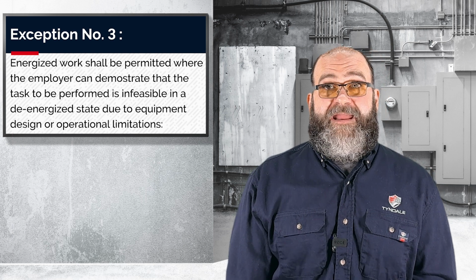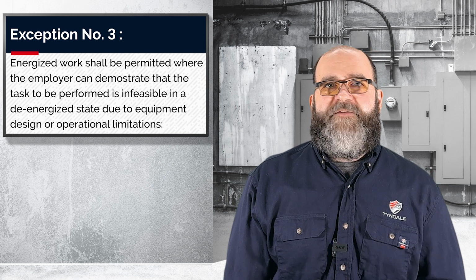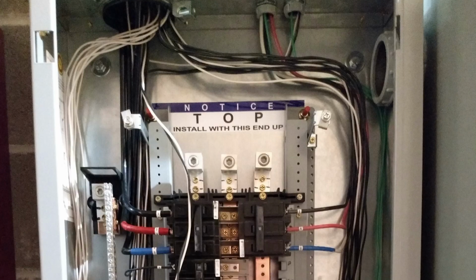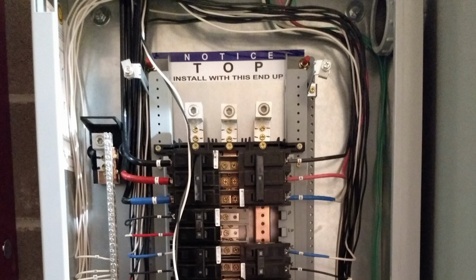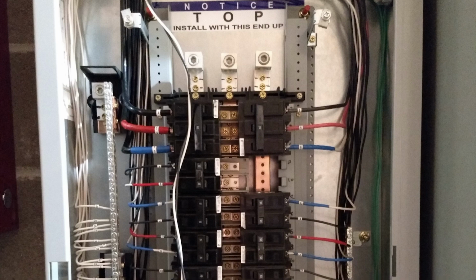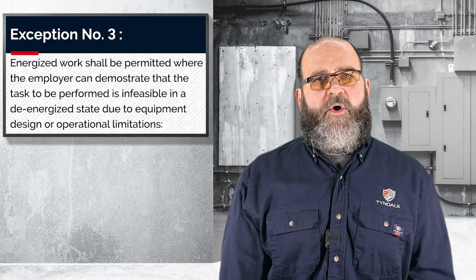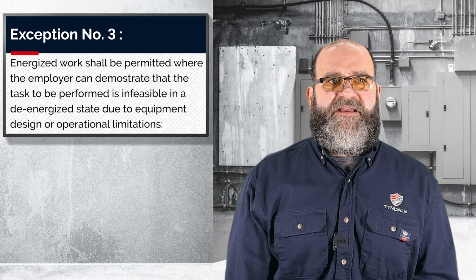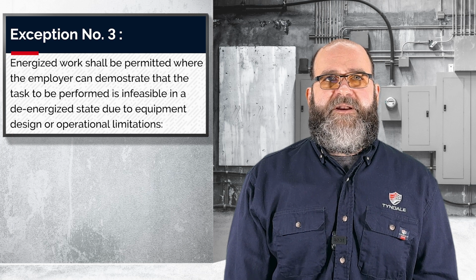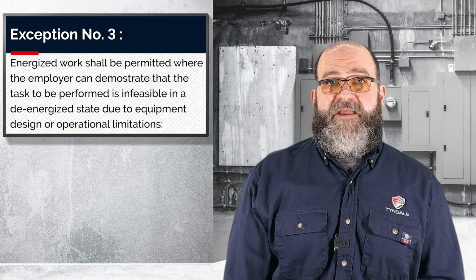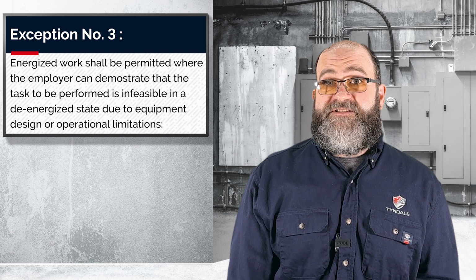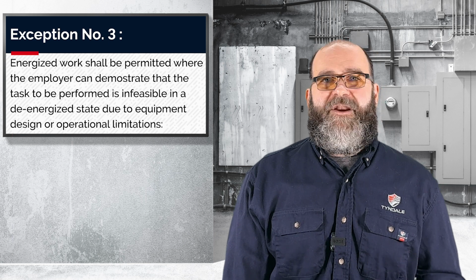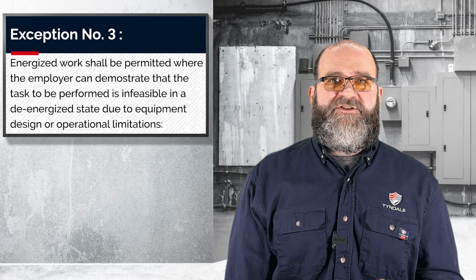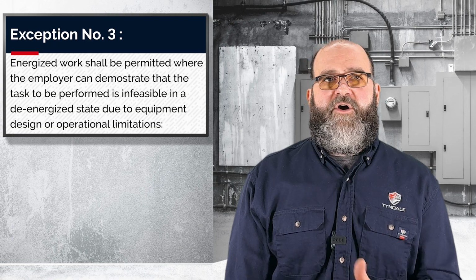impractical. Meaning, if you have a panel that has a breaker inside of it that runs your data center, and you need to install a new breaker in that panel, it is impractical, not infeasible, right? You don't want to shut it off because your data center is connected to it, but it's not going to kill somebody. You're required to turn off that panel to install that new breaker per the 70E. This task is not worth the risk of injury or death from shock or arc flash.